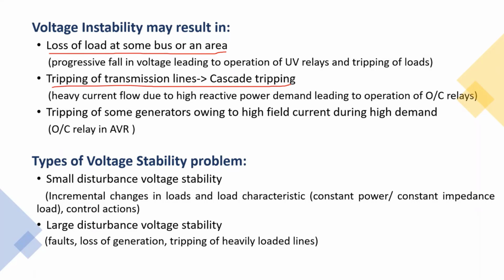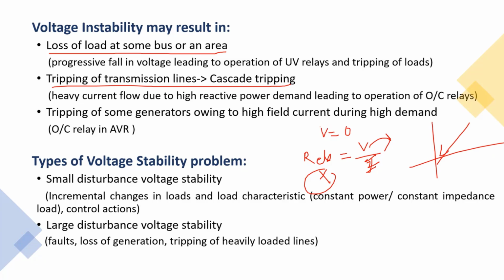Why is this voltage instability very dangerous for the transmission people, particularly substation people? Let us say if voltage is zero, all the relays see it basically as V by I, the apparent impedance. If the voltage is getting to a lower value, then your apparent impedance will encroach into the protection zone. This results in the operation of different kinds of relays in the system. So this is one of the problems that we face during voltage instability. Many of the transmission protections can operate in that situation.